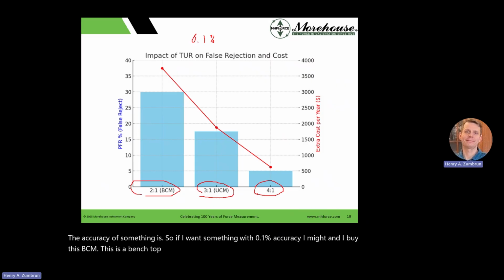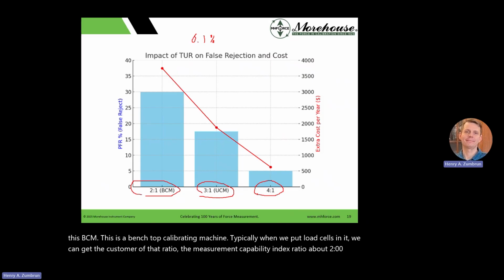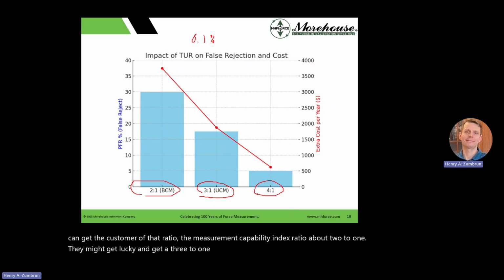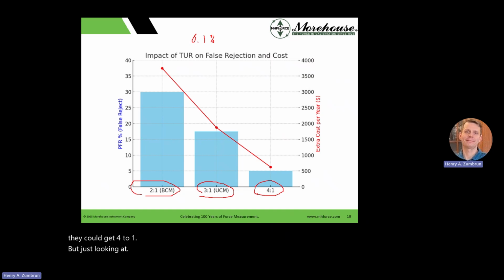Typically, when we put load cells in it, we can get the customer that ratio, the measurement capability index ratio, about 2 to 1. They might get lucky and get a 3 to 1. I'm being very conservative here. With a universal calibrating machine, they're probably going to get 3 to 1. If they have automated, they could get 4 to 1. But just looking at this price tag of ownership, you can see extra cost per year for this equipment.